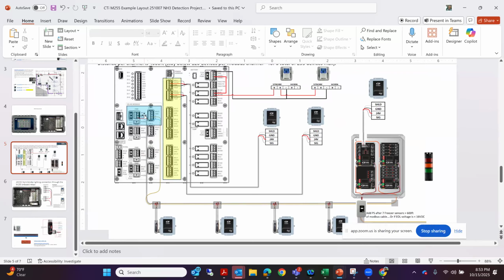And that basically tells this system, when it shoots the frequency out and it gets down to here and bounces back, that that's the last board. So it keeps the communication straight, right? And so anyway, that's how Modbus actually works, as compared to like right here.